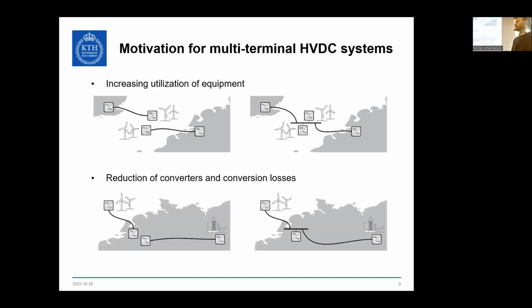Another benefit or potential optimization is what I like to call the German example. To the left, you have a wind farm connecting to the onshore network, but the high load areas are to the right, some big city, which means that to transmit the power down to the cities, you need to build an additional link. In case there isn't big demand on the coast, you can basically remove one converter, giving a 3-terminal system instead. In addition, if the power is flowing from the wind farms to the city, instead of converting AC to DC, DC to AC, AC to DC, DC to AC, you only have 2 conversions: AC to DC and DC to AC. So you also reduce the losses.